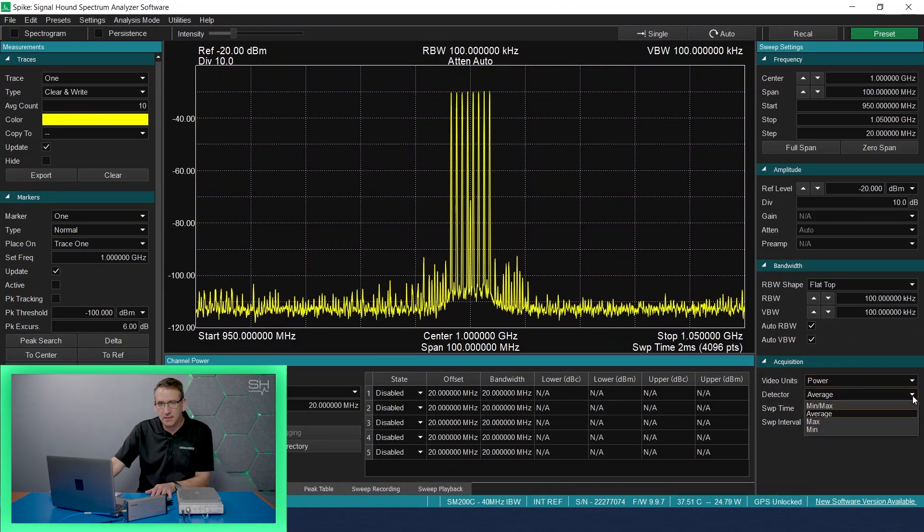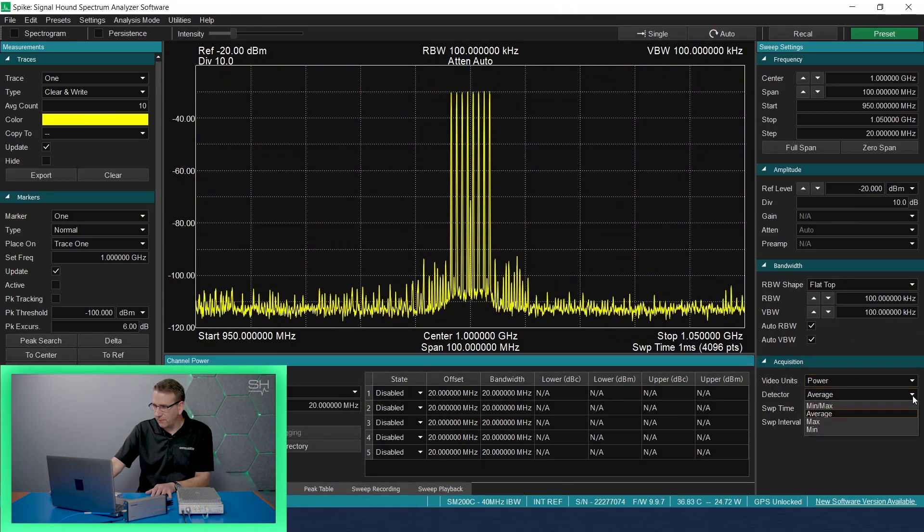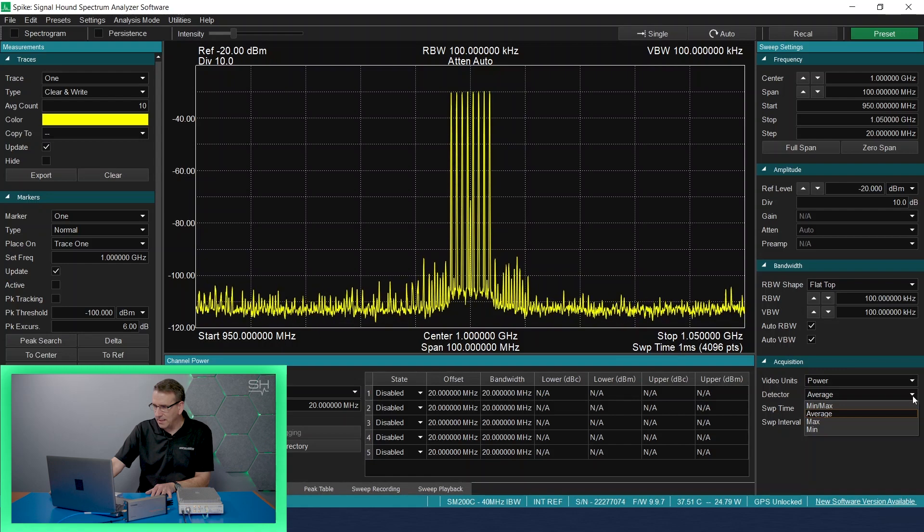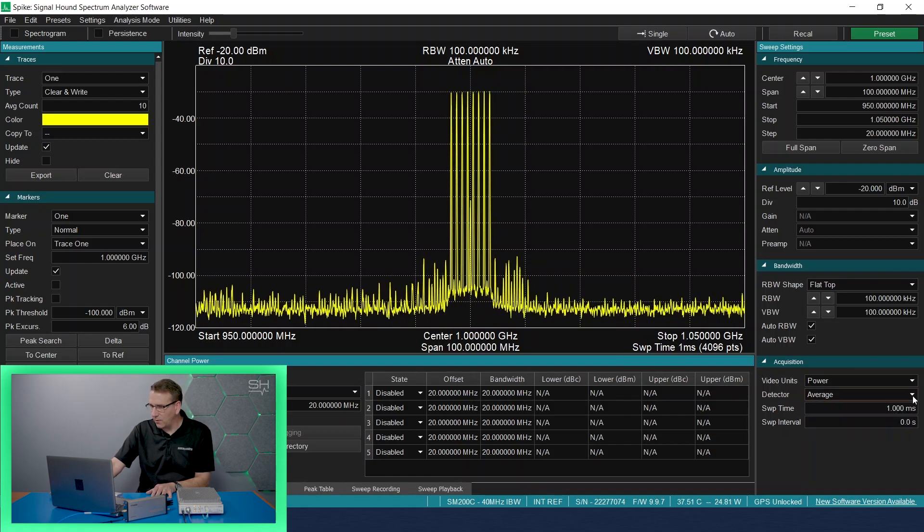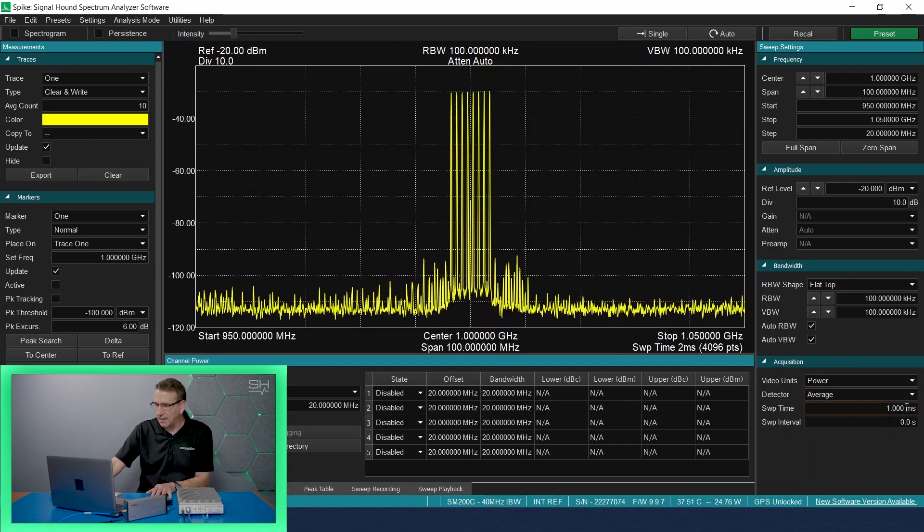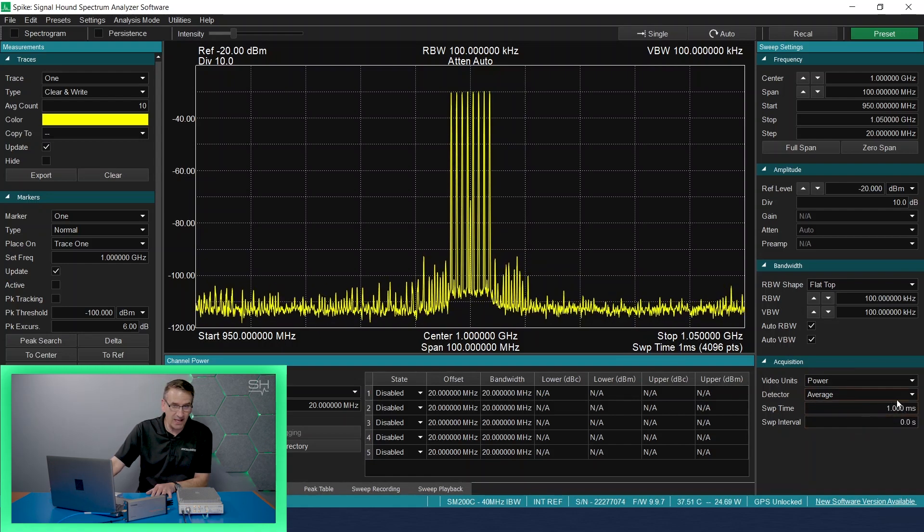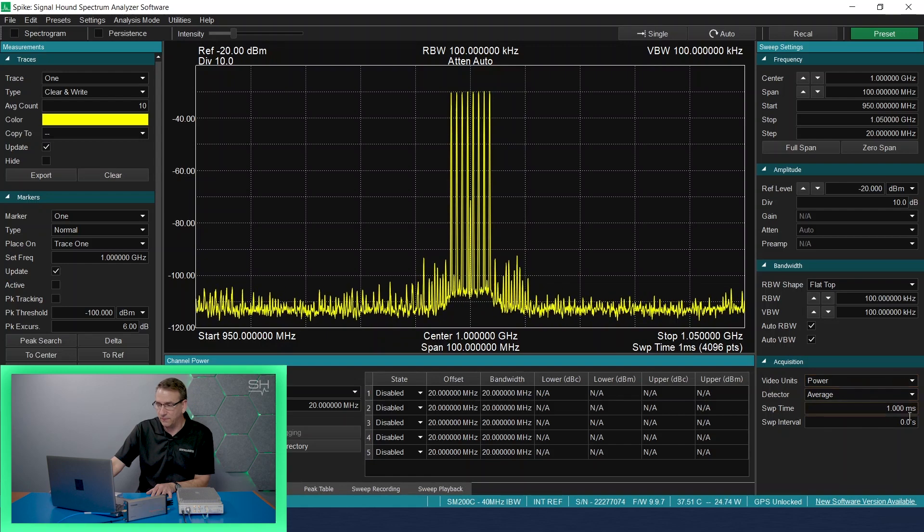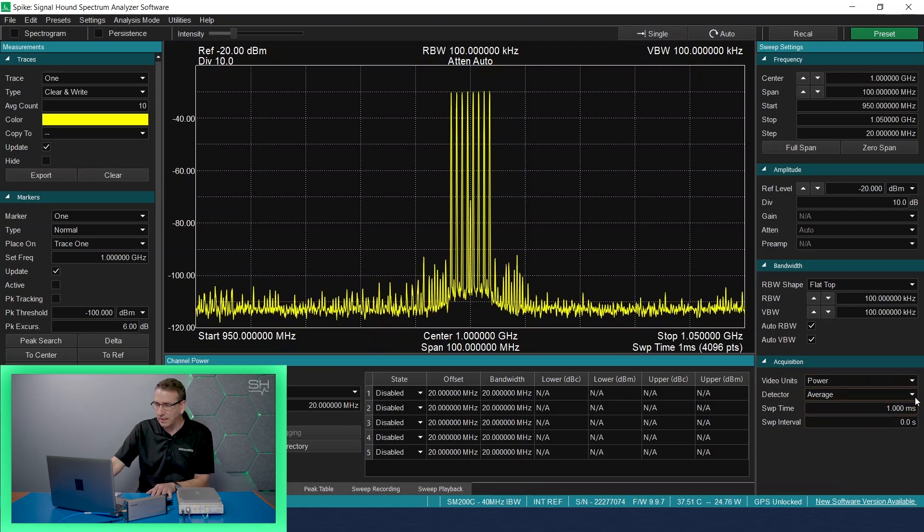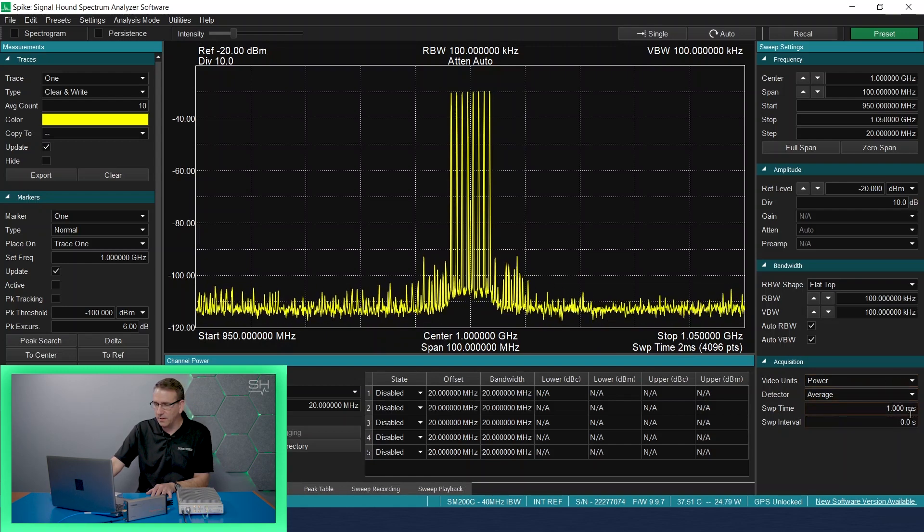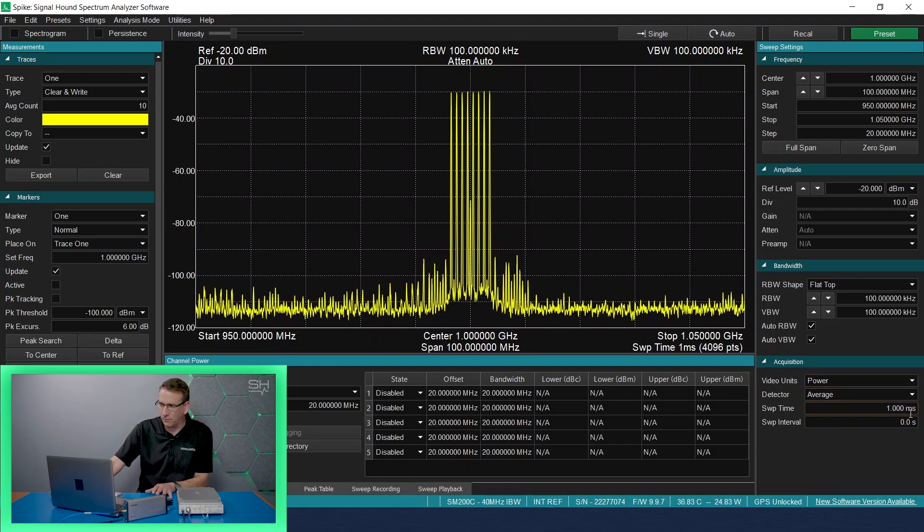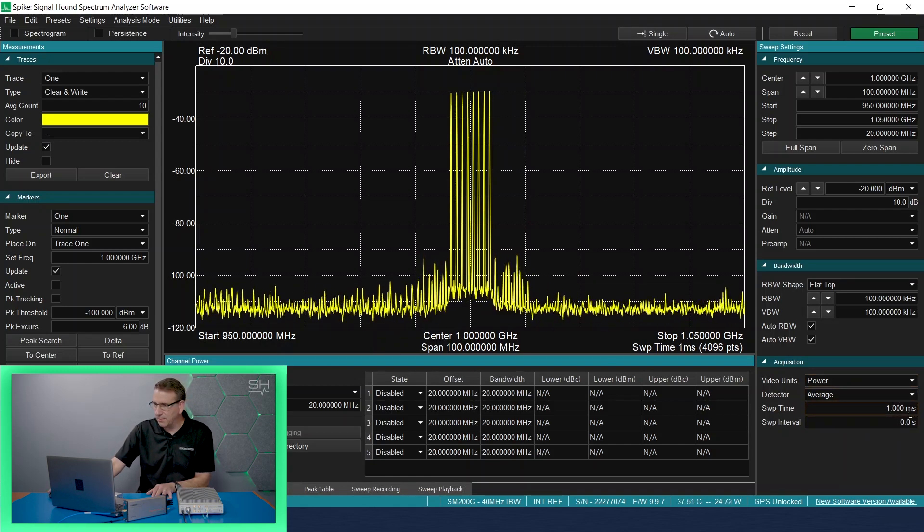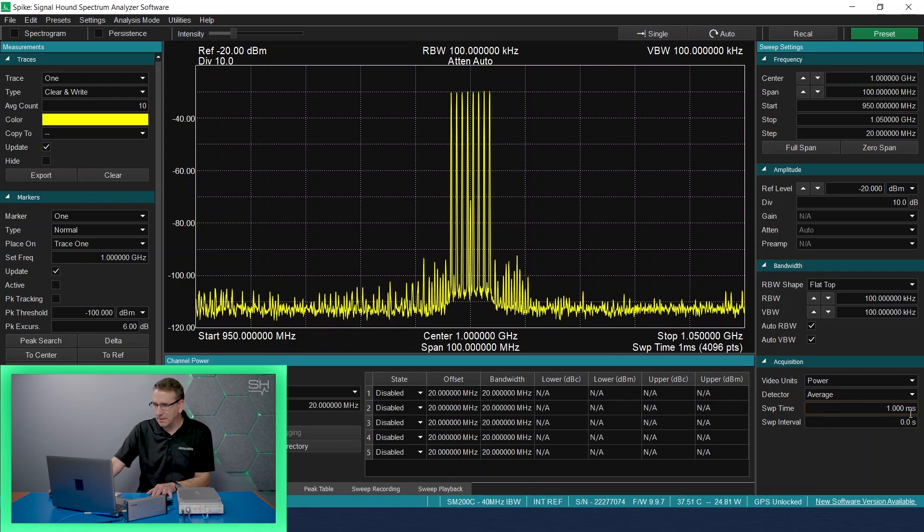We can adjust the detector from an average detector to min/max, and we can also set and adjust the sweep time and the sweep interval, rather than letting the software determine what the sweep time and sweep interval will be based upon your span settings.